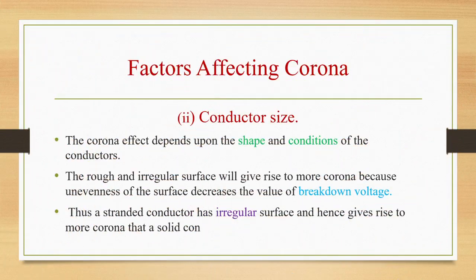The second factor affecting corona is conductor size. Corona effect will depend upon the shape and conditions of the conductors. A rough and irregular surface will give rise to more corona because unevenness of the surface will decrease the value of breakdown voltage. So a stranded conductor has an irregular surface and hence gives rise to more corona than a solid conductor.